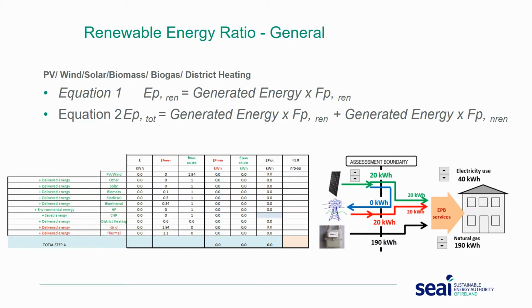Similarly, for biomass or biogas, it's not quite clear on that screen, but if you look at bioethanol or biodiesel, it's probably more easily read, you can see that the non-renewable primary energy factor for that is 0.3, and the renewable primary energy factor is 1. So the total primary energy factor for all of it is 1.3. So only one out of the 1.3 is regarded as renewable. Similarly, with district heating schemes, we'll be determining what the renewable contribution is for that district heating scheme versus the non-renewable contribution. And again, we're in talks with the likes of Dublin City Council and Codema for the likes of the Poolbeg incinerator district heating scheme, those kind of systems, where we will be defining what the renewable contribution is from those systems and including it in the calculation.